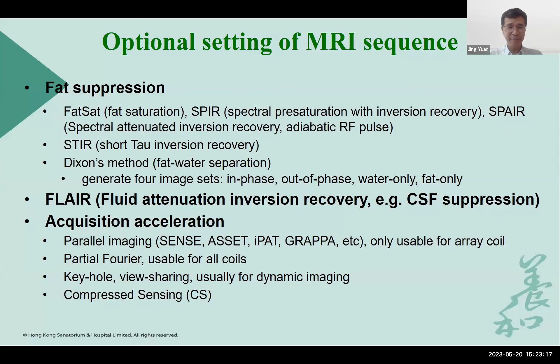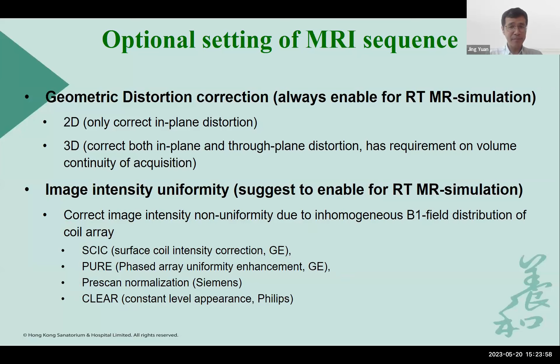For simulation scans, high geometric fidelity is crucial. So always enable the geometric distortion correction on your MRI console, either 2D or 3D, for MRI simulation scans, to accommodate the MR-CT registration. MR image intensity non-uniformity correction algorithms are also usually enabled for a simulation scan. They have different solutions or different names on different vendors' MRI scanners.